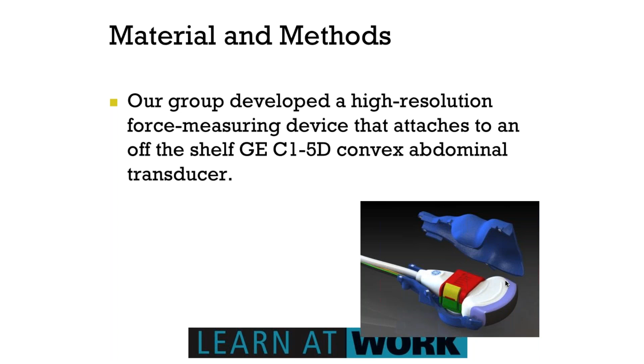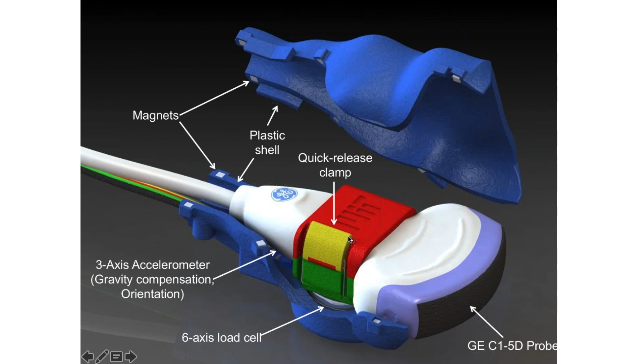So the MIT group and the Mass General group, as a team, we developed this high resolution force measuring device. The first version of it was developed on a GE C1-5D abdominal transducer, but since then we've also been using it on several different transducers made by different manufacturers. As I go through it, it's essentially made up of very simple components. There's a clamp that goes onto the transducer, and within it is the force measuring 6-axis load cell that can measure the forces, without getting into too much technical detail. But as you will see here, this clamp with the device within it can be designed for any probe. And towards the end, I can speak a little more about why I mention that particularly.